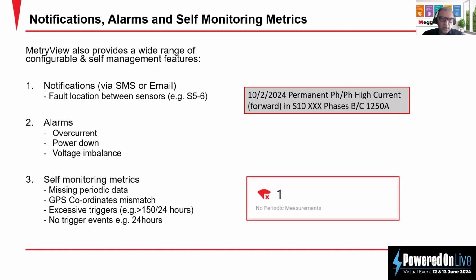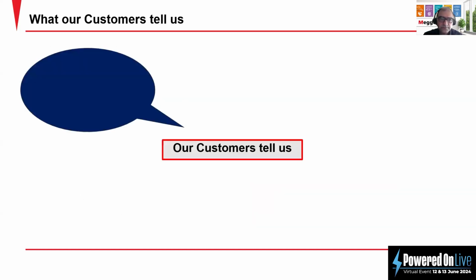Additional things are notifications, alarms, and self-monitoring metrics. Sensors can be set to send notifications via SMS and email to the line crew, and it shows the time and date of the fault, the type of the fault, which sensor is sensing it, and the direction of the fault. You can set alarms like overcurrent, power down, and voltage imbalance, and some self-monitoring metrics like missing periodic data, GPS coordinate mismatch, excessive trigger or no trigger events.